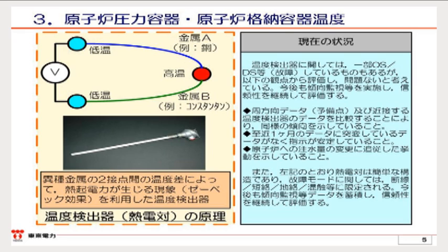We are not sure whether the accuracy of the detectors of each thermometer is within the limits of calibration or not, but according to the overall trend, we think that such temperature estimates will be probable. Also, recently, we can change the water injection rate to the reactor, and it appears as a temperature shift. Therefore, we think that the soundness of the thermometer is secured.